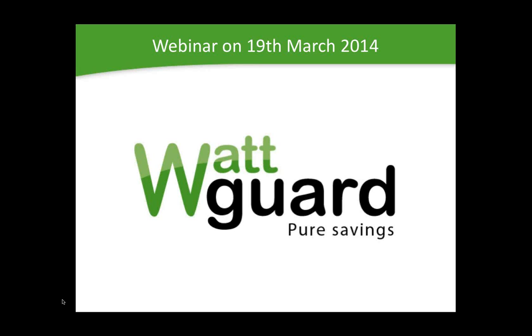Yeah, we would always separate those units. So say for instance that you have two parts of a factory. One part you have T8s, and another part you have LED or electronic ballast type of T5. Then we would only go for the circuits that are supplying the T8s. If some of the circuits have a mix of light units, there are two possibilities. Either we just agree not to make an installation, because we do not want to have a mix of units controlled by the Wattguard, for safety reasons and operations reasons.